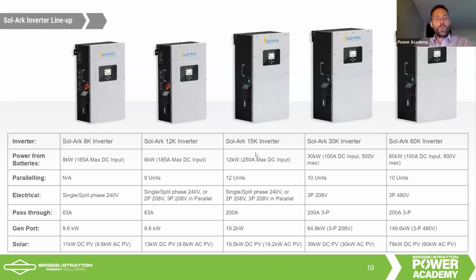The 15K, I'll point out some things. So it's capable of inverting 15 kilowatts of power. 12 kilowatts of that can be inverted directly from the batteries. The additional 3 would come from solar, or if you have more coming from solar, it could use less from the batteries, etc. But capable of producing 15 kilowatts from the DC side. So your solar and your batteries, DC solar and DC batteries. You can parallel up to 12 of these units. So if you have a very large installation, you can parallel 12 units to power it.